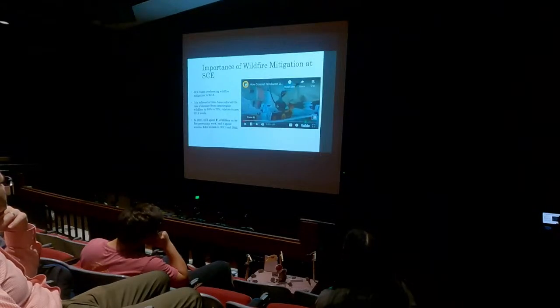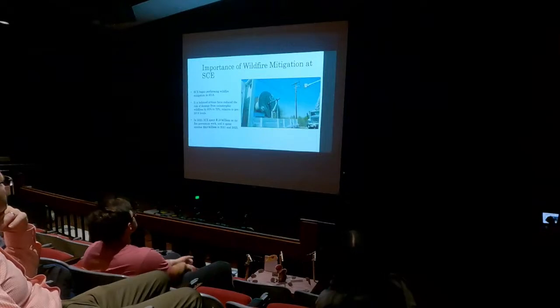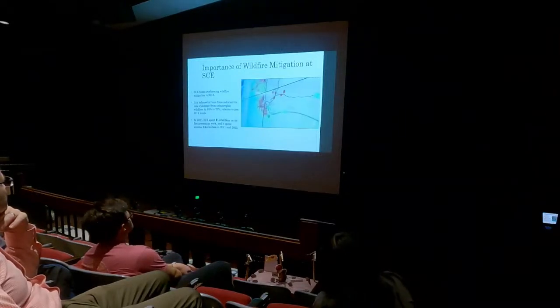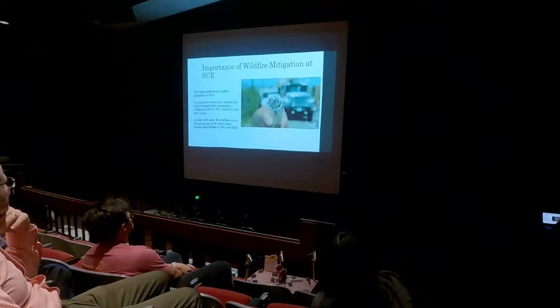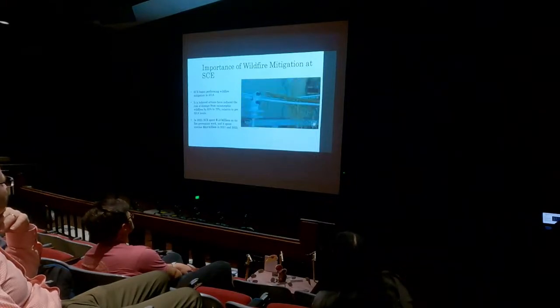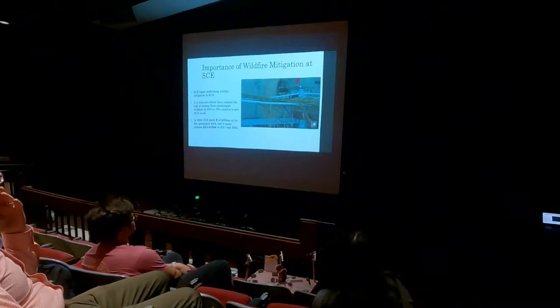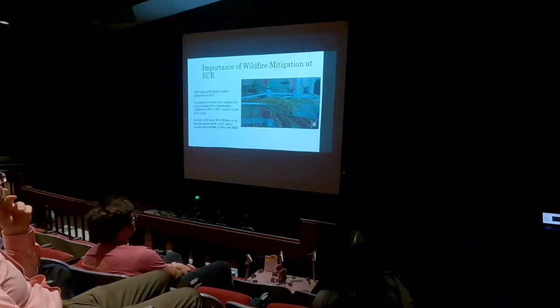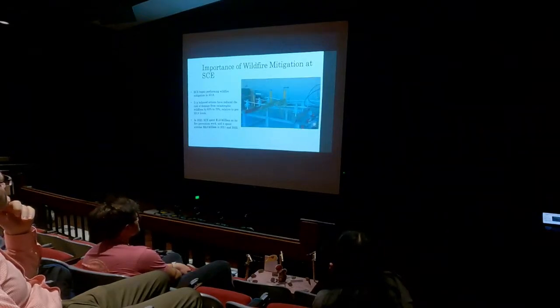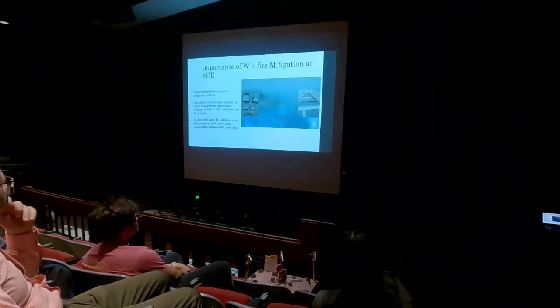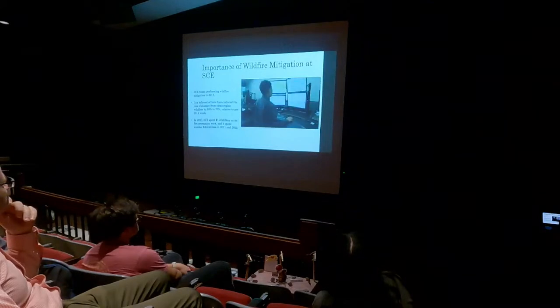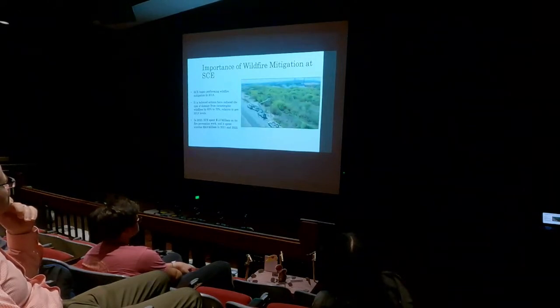SCE recently conducted a demonstration to show the benefits of insulated wire in high fire risk areas and why power may be shut off during windy, dry conditions. Insulated wire, sometimes called covered conductor, has insulated material covering the bare wire, which significantly reduces the possibility of sparking if foreign objects like tree branches or palm fronds blow into our lines. In this demonstration, we laid various objects on insulated wire to show that even at high voltages, there was no arcing or sparking. However, when similar objects were placed on bare wire, they started to arc and spark. This is why we implement public safety power shutoffs during high wind conditions when vegetation has dried out, and why we are installing insulated wire.